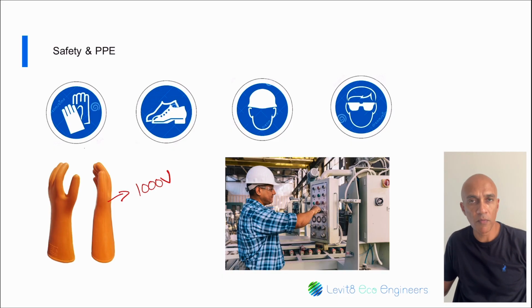And as mentioned, minimum 1000 volts because you'd most likely be measuring low voltage installations, or if you're measuring at medium voltage, you're going to be measuring on a 110 volt voltage transformer as we discussed previously. Okay. It is also good to wear safety shoes with thick rubber soles to ensure good insulation of your body to ground. So safety shoes are also essential. Then your client may have requirements for hard hats and safety goggles, and those are also recommended to wear because you never know what type of dangers or hazards are going to be present when you are carrying out measurements.